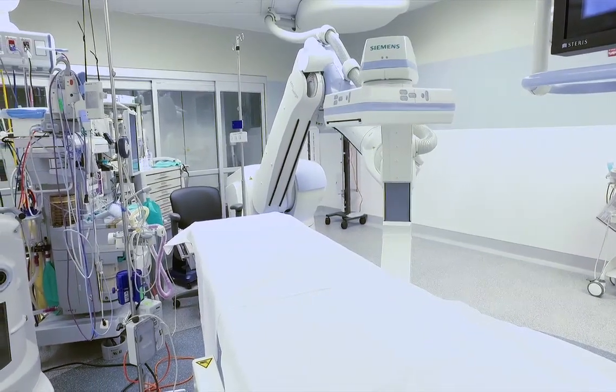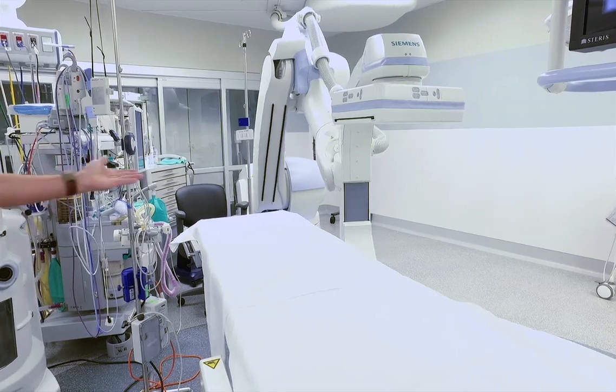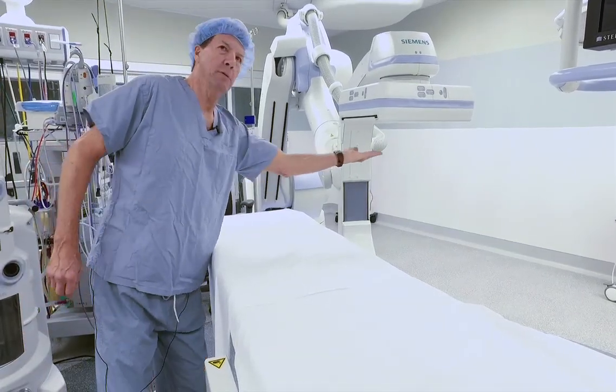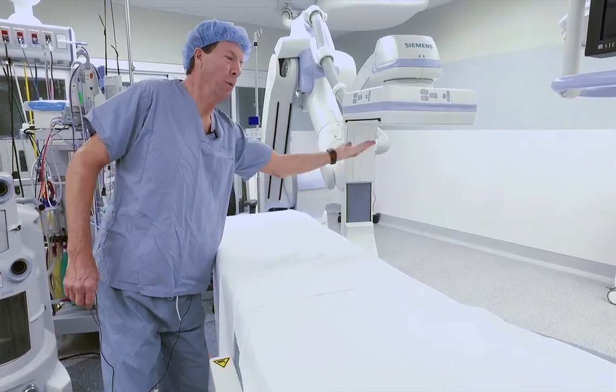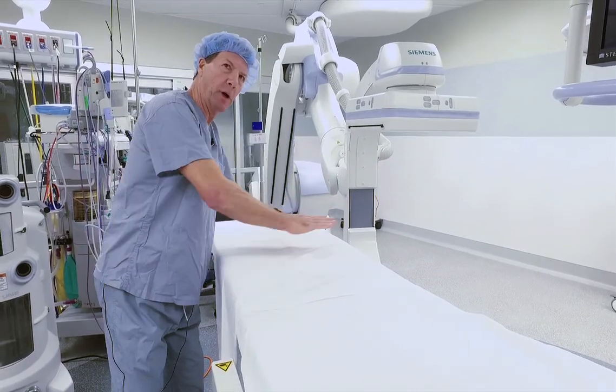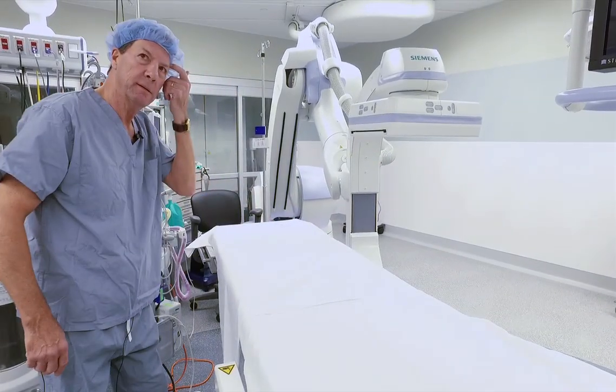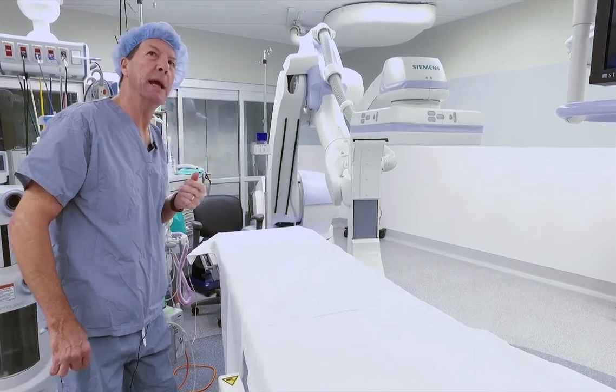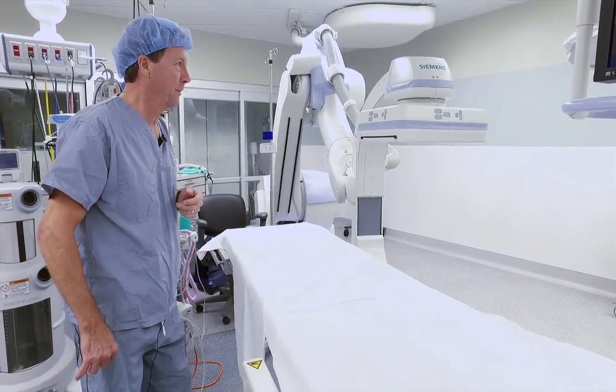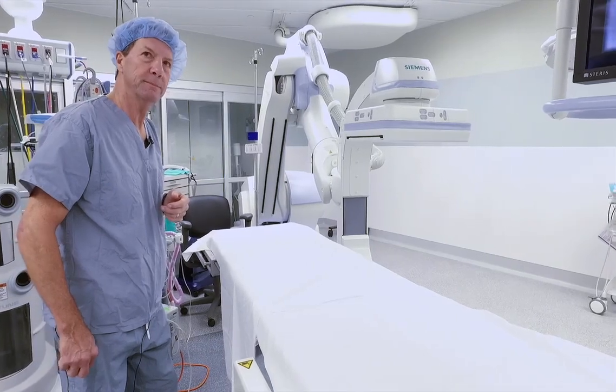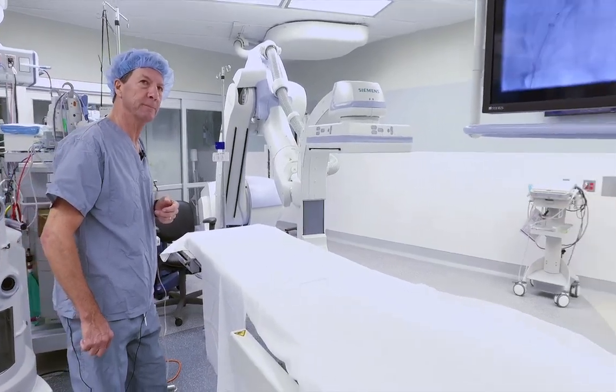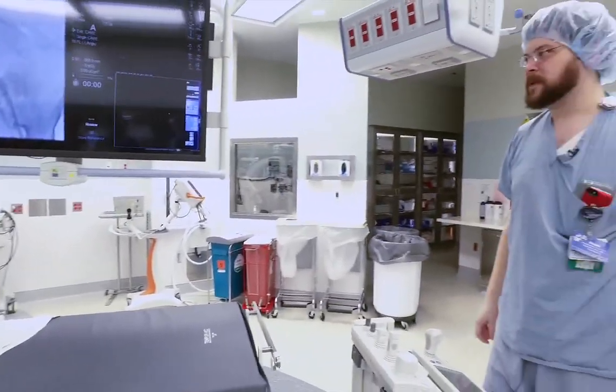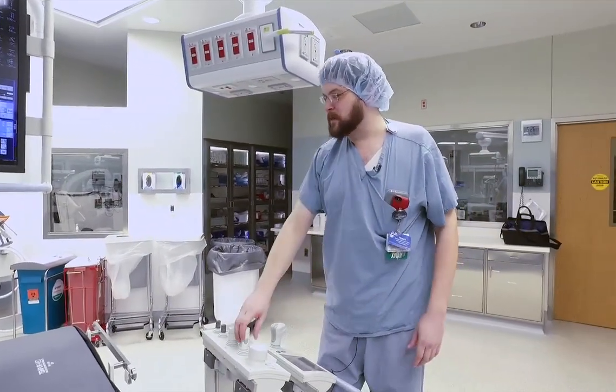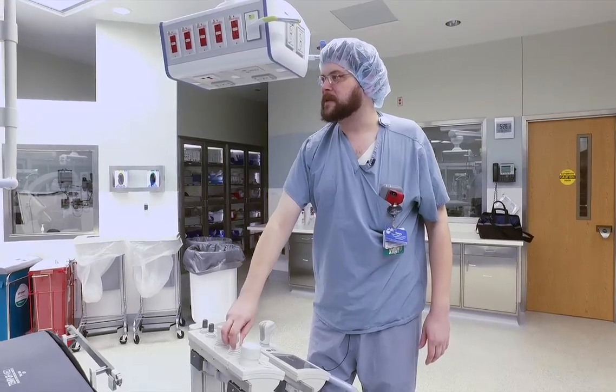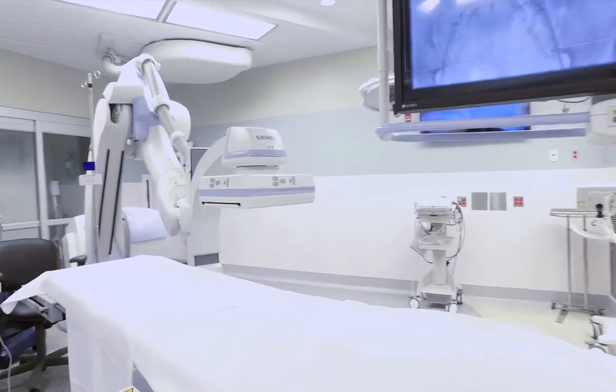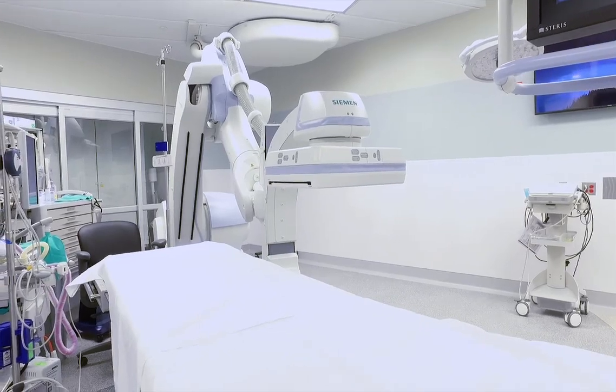Now the arm, and I'm going to point at this now, I'm not going to touch it, but the arm has some kind of a vision or some kind of a signal coming out of the bottom that it's reading on the patient here? The bottom of the machine is emitting X-rays. Those are detected by a detector on the top plate. In a normal X-ray machine, the X-ray would come from the top down. In a C-arm like this, it comes from the bottom up. So essentially, because of geometry, we can do things like this. By bringing that closer to the patient, we reduce what's called magnification of the X-ray image.